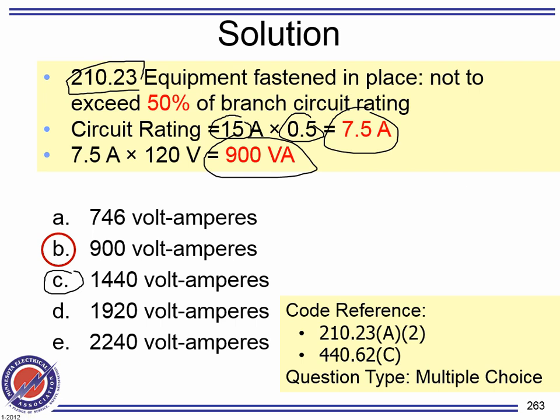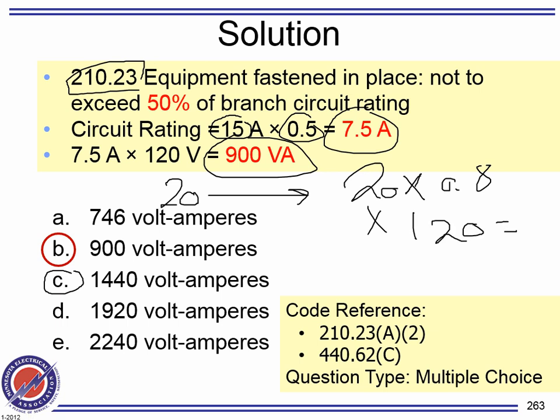Now, if my circuit is an individual 20 amp circuit, then what you do is you take the 20, multiply it by 0.8 to find the volt amps, and multiply it by 120. I think that will be 1440. Is it? No? 1920. Okay, so the 1440 maybe is if it's 15. So they put it to you as an option, guys. If you did the 0.8, you'll find an answer, think you got it right, and it's wrong. One more time: shared circuit with AC units, 50%. Individual circuit to the AC unit is 80%.